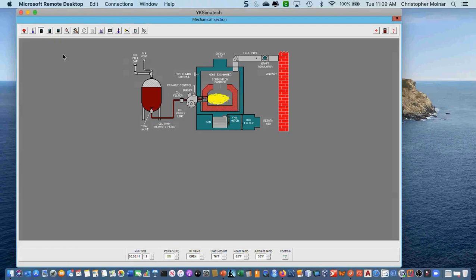We have a draft gauge. We can put the draft gauge into the flue pipe. I have a negative 0.05 draft. That's within our safety ranges. Okay, I have a combustion analyzer. I can get things like stack temp. Okay, I can get things like net stack temp.